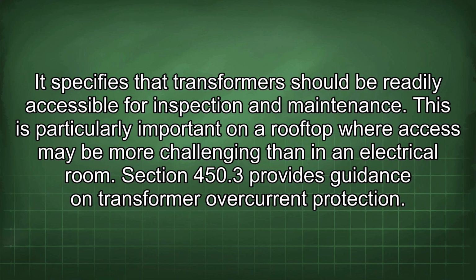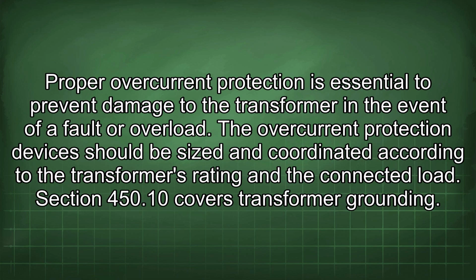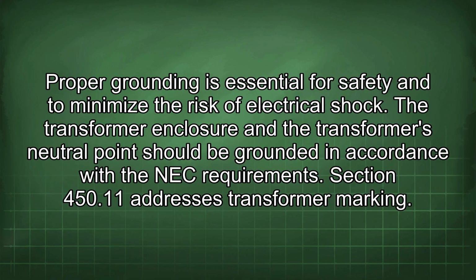Section 450.3 provides guidance on transformer overcurrent protection. Proper overcurrent protection is essential to prevent damage to the transformer in the event of a fault or overload. The overcurrent protection devices should be sized and coordinated according to the transformer's rating and the connected load. Section 450.10 covers transformer grounding. Proper grounding is essential for safety and to minimize the risk of electrical shock. The transformer enclosure and the transformer's neutral point should be grounded in accordance with the NEC requirements.